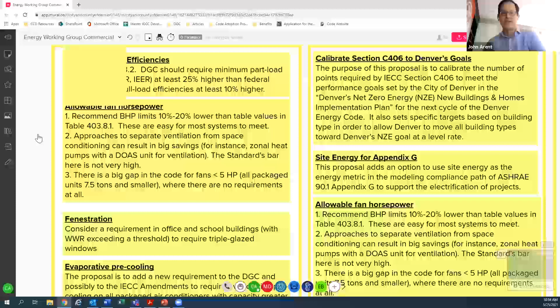Secondly, and this is something that's been done heavily in Washington State, is looking at approaches that separate the ventilation from the space conditioning. So if you have something called the DOAS, or dedicated outside air system, that system can provide tempered air for ventilation needs of the building. And then the main heating and cooling systems, rather than running continuously, can cycle on and off with the loads. So you have potentially a net fan energy savings. This is especially useful for buildings that have smaller units or large numbers of smaller units for individual zone control, where they can use this for savings. Larger systems will typically have variable speed drives for modulating the fan down. So there would be a lower degree of savings for those types of system configurations.